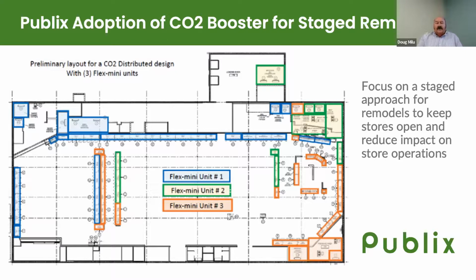So that's a bit of a logistical challenge when you're dealing with structural integrity of the existing roof. We may have to do more bracing of our bar joists overhead to accommodate multiple units in one location, or move temporary units off to the side along the column lines for better support to facilitate installation of the new unit. Logistically it's a challenge, but once we have that worked out on paper, typically our remodels run anywhere from 90 to 120 days.